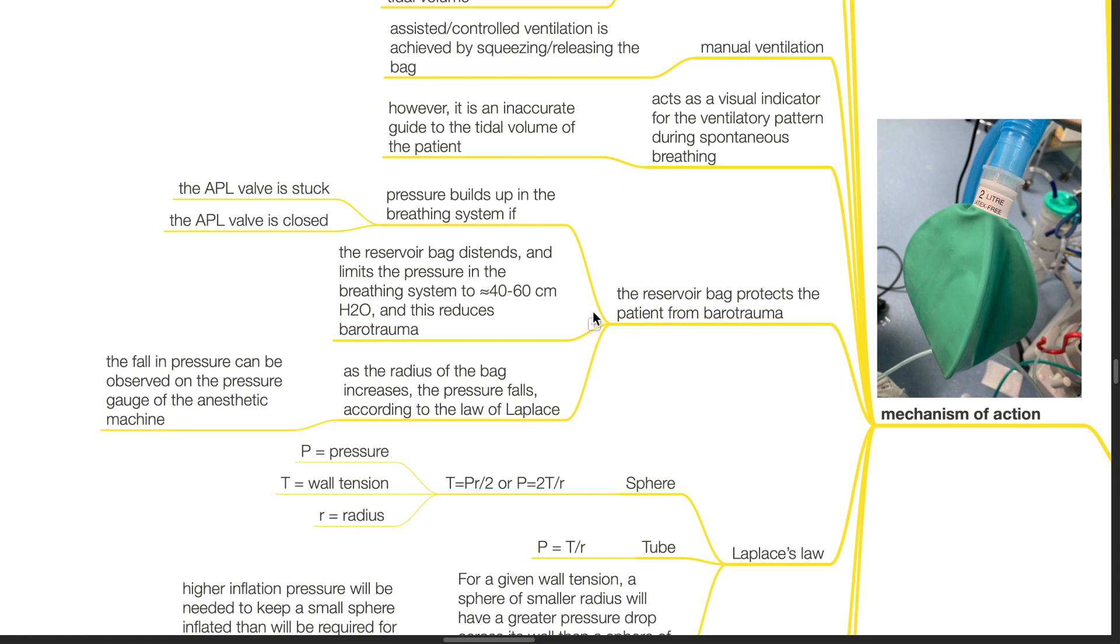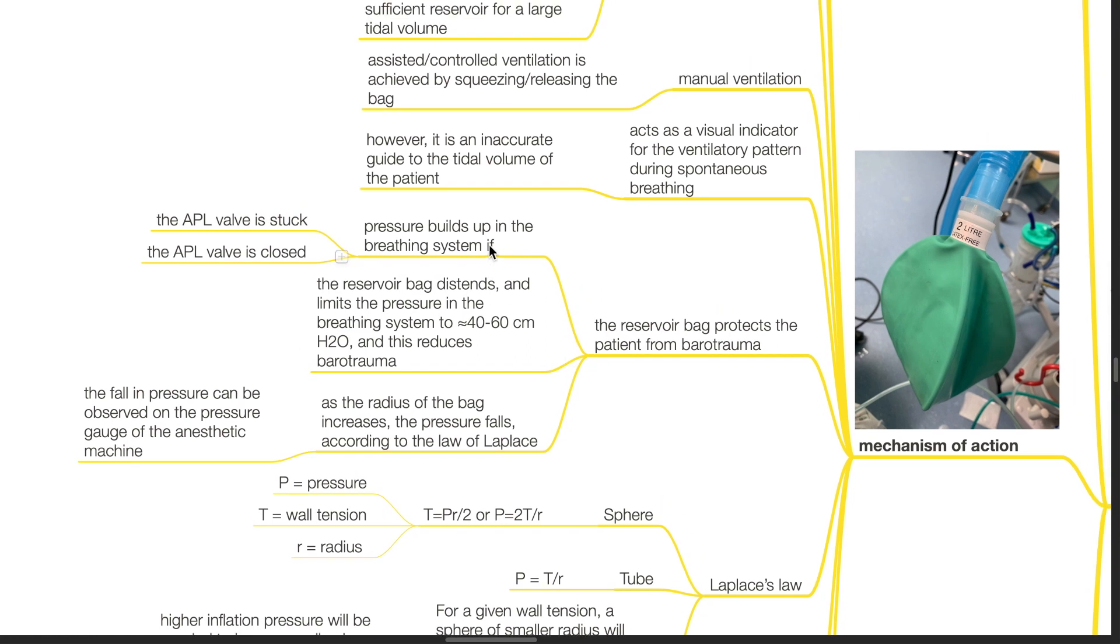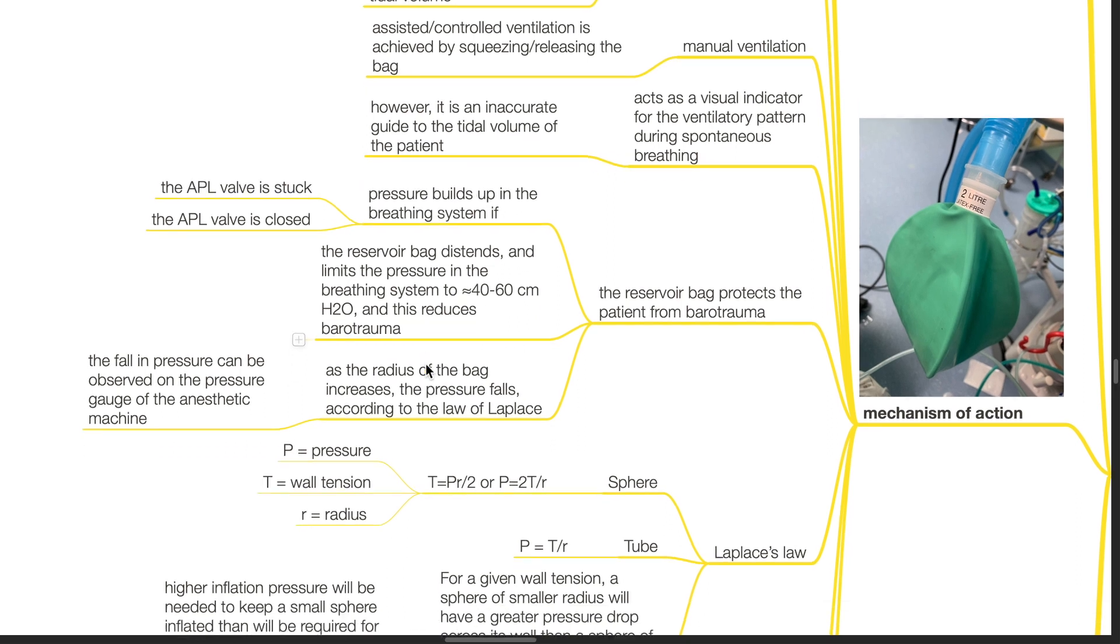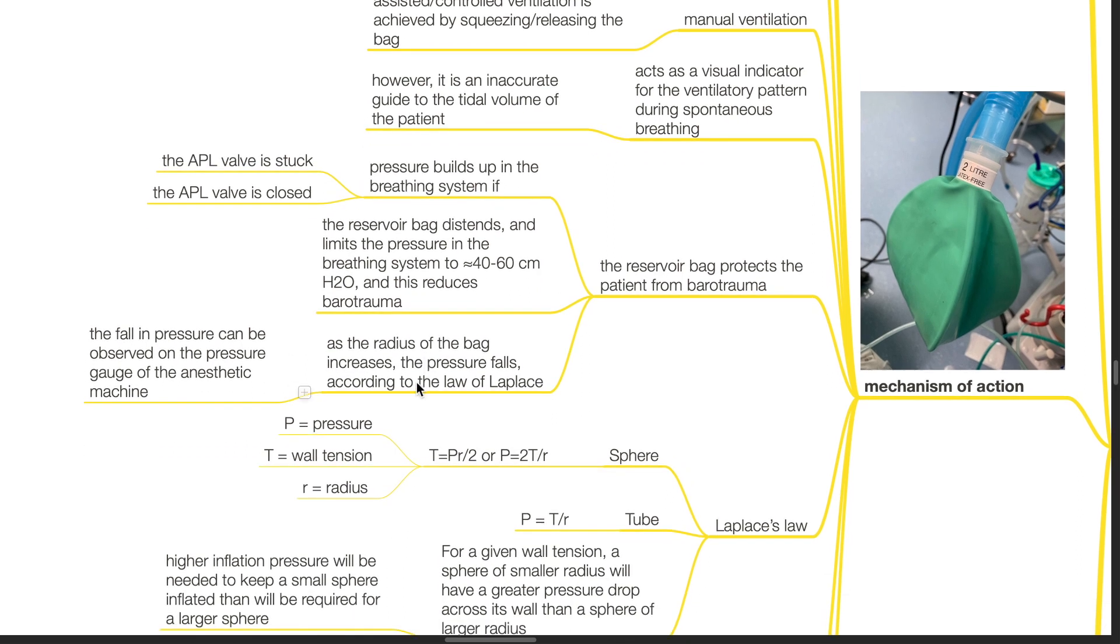The reservoir bag protects the patient from barotrauma. Pressure builds up in the breathing system if the APL valve is stuck or closed. The reservoir bag distends and limits the pressure in the breathing system to 40 to 60 CMH2O and this reduces barotrauma. As the radius of the bag increases, the pressure falls according to the law of Laplace. The fall in pressure can be observed on the pressure gauge of the anesthetic machine.